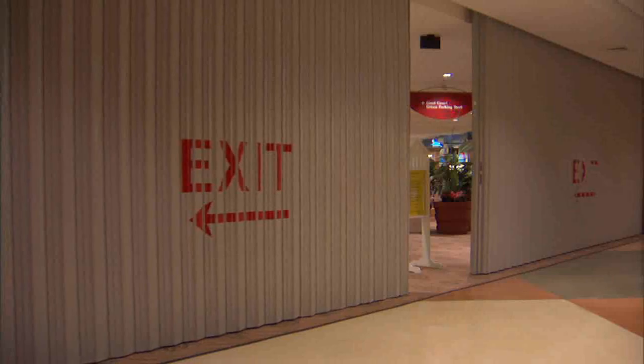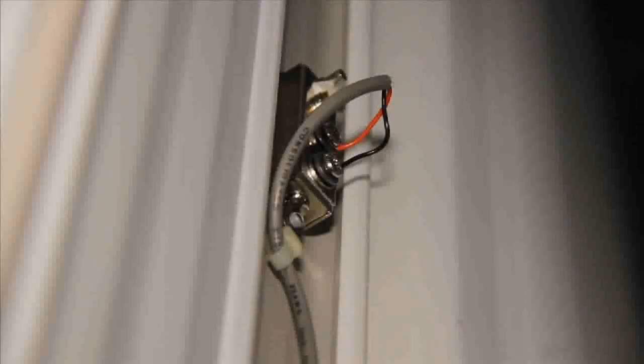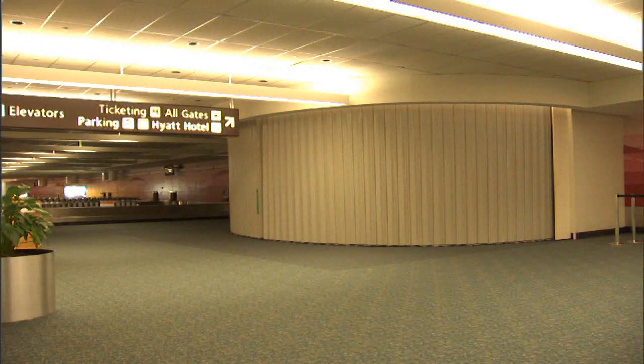The thermal lockout feature is under microprocessor control and continuously monitors ambient temperature at the door through a dedicated input channel. In the fire alarm condition, if the temperature on either side of the door reaches 500 degrees Fahrenheit, all functions that would automatically open the door are disallowed. This feature assures fire containment.